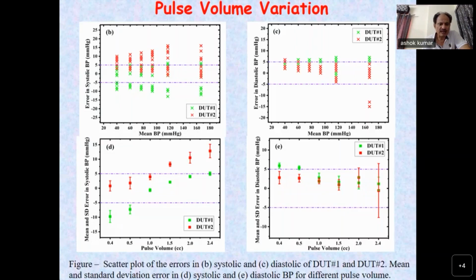So this is the conclusion of this. Here are device under calibration 1 and 2. You will see that if the pulse volume is less than 0.5, device 1 has a mean and standard deviation larger than 5 mmHg, meaning this device failed to provide the real blood pressure for a person with pulse volume less than 0.5 or 0.6 cc. It means it cannot give the correct blood pressure value for unhealthy people having problems. Then we did the same for systolic and diastolic measurement. Next slide, because this is all science.